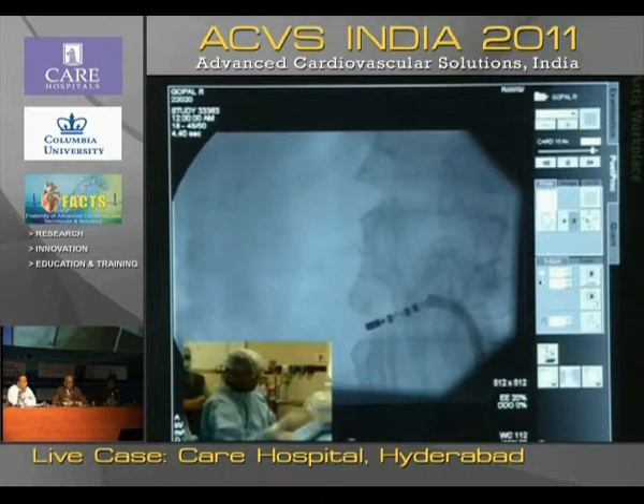We have first gone to the inferior aspect of the renal artery. Because this is a 4 millimeter tip catheter, the density of the current is low because the electrode size is larger compared to the Symplicity catheter used in the Symplicity trial. They used 8 watts, we use somewhere from 15 to 20 watts, and because this is a narrow chamber, you will have an impedance of somewhere around 250 to 300. Let's just measure the impedance of this. Connect this please.